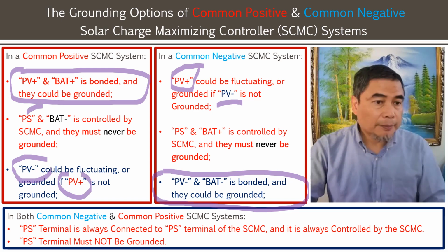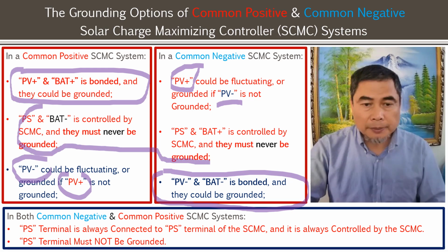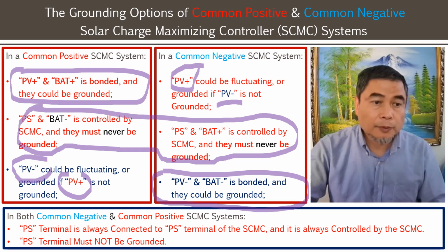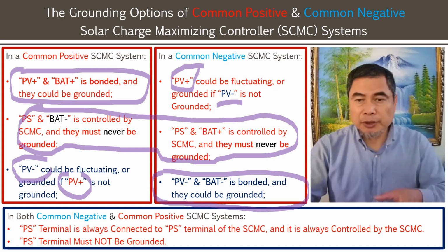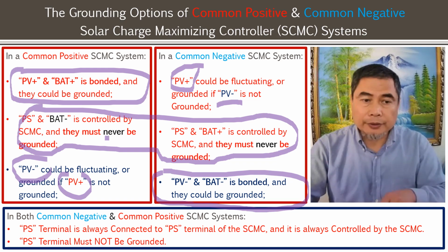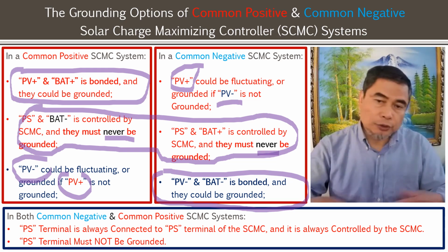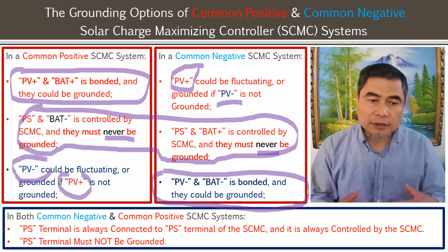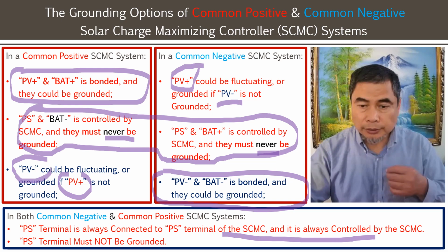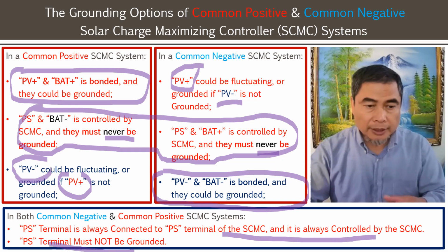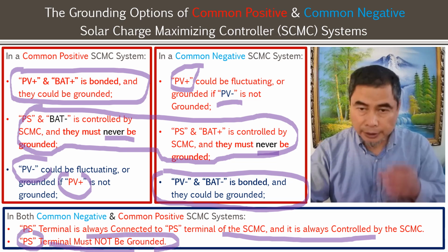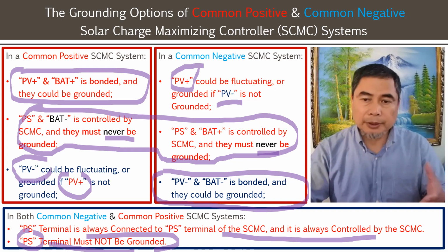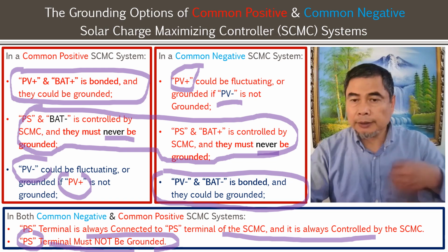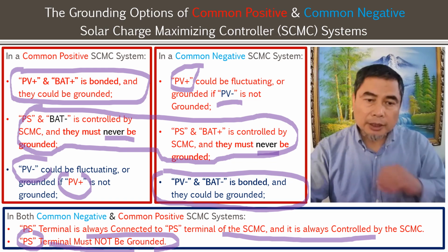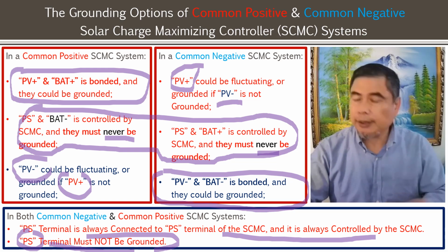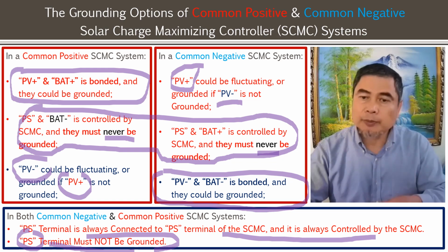But in any case, in common positive or common negative design, the PS split wire, matching the battery's nominal voltage, is never to be connected to the ground, because it has to be controlled by the switch inside the solar charge controller. It always gets controlled inside the solar charge controller. That PS terminal is never grounded. So just keep in mind which part can be grounded and which part cannot. It depends on the common positive or common negative design. But no matter what, the PS terminal is never grounded, because it always gets connected to the solar charge controller to be controlled.